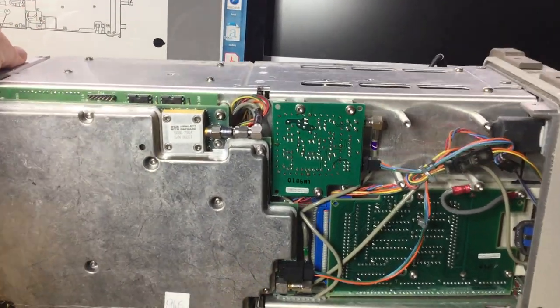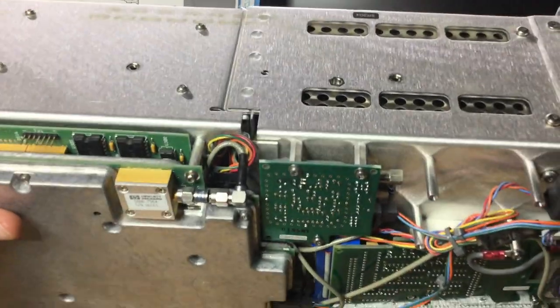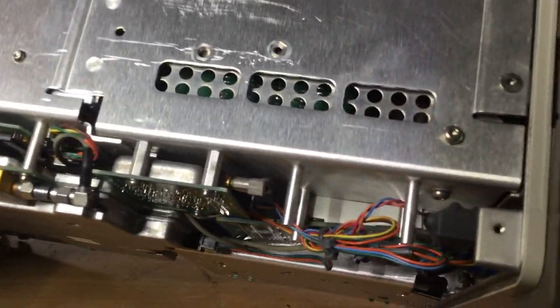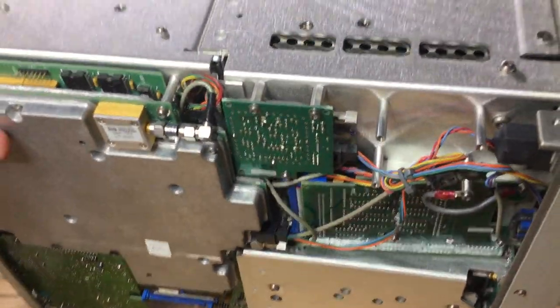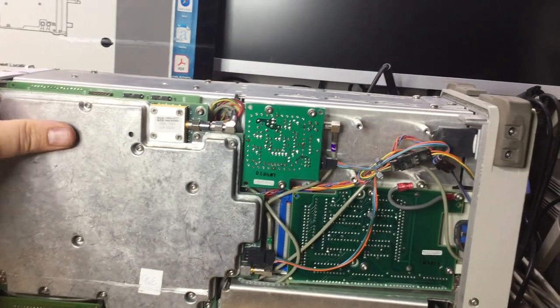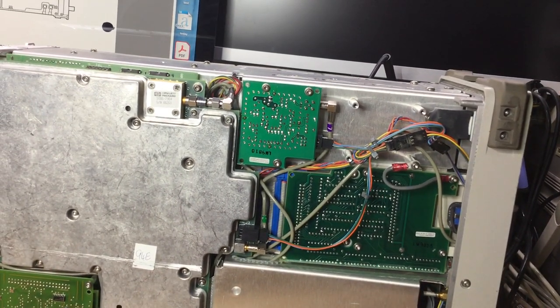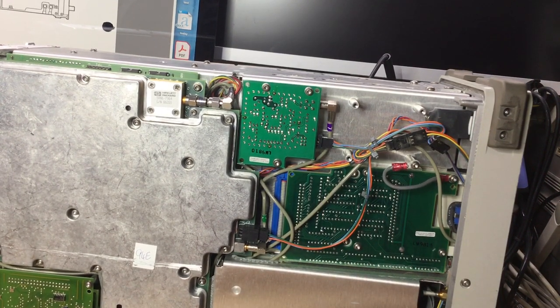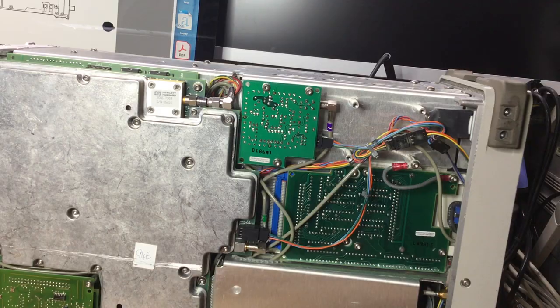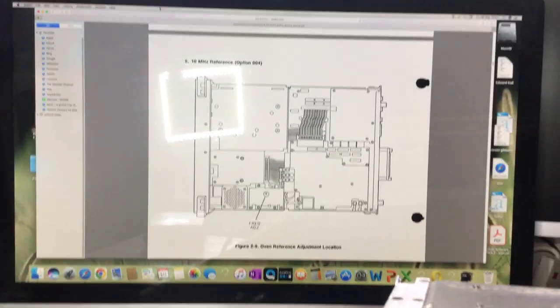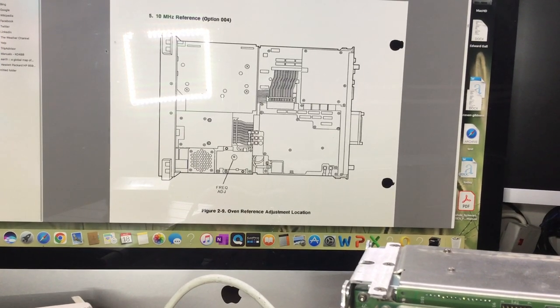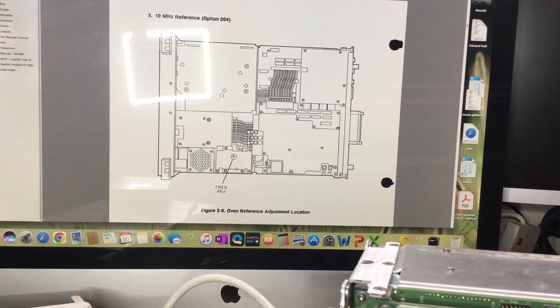If I just carefully turn it over a little bit, you can just see there that there's the reference oscillator module down there. But there's no signs of any adjustment potentiometers or anything like that, so it must be adjusted through the software, the calibrate screen. Now the calibrate screen is password protected. It's got some kind of passcode that you need to enter in order to get into the service cal menu, so I need to find that out now in order to unlock it so that I can make the adjustments through the software.